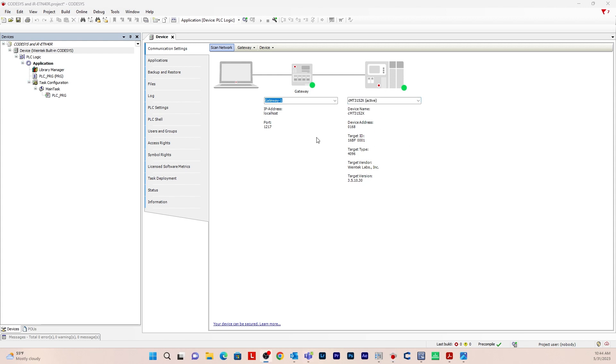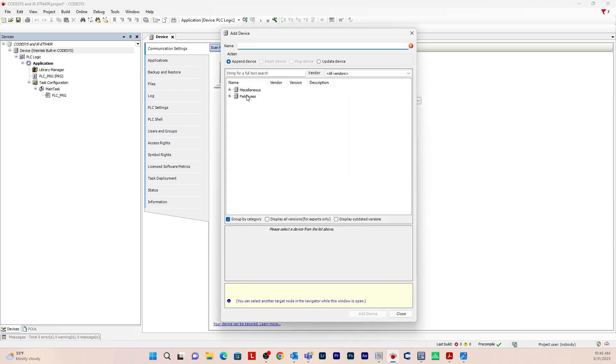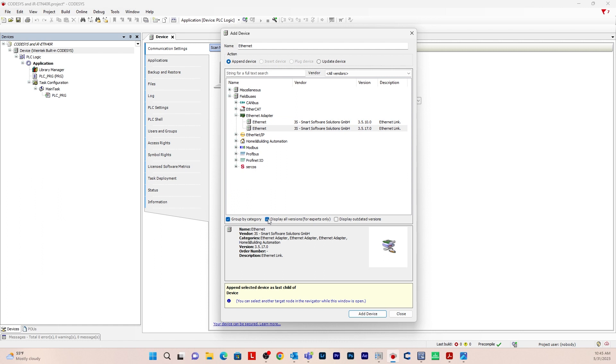After you establish a connection with the CMT device and CODESYS, you'll want to add an ethernet device. So right click on device, go to add device, and then field buses. Drop this down. Go to ethernet adapter, ethernet, and display all versions. I'm going to use 3.5.10, that's the version I'm using.